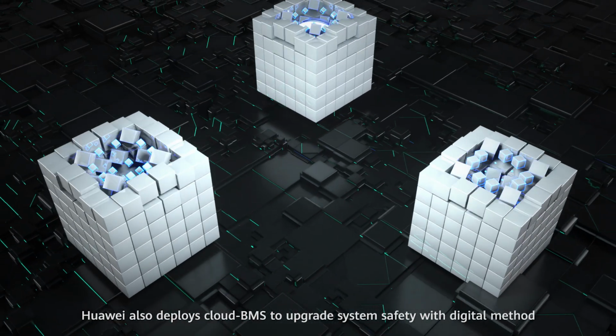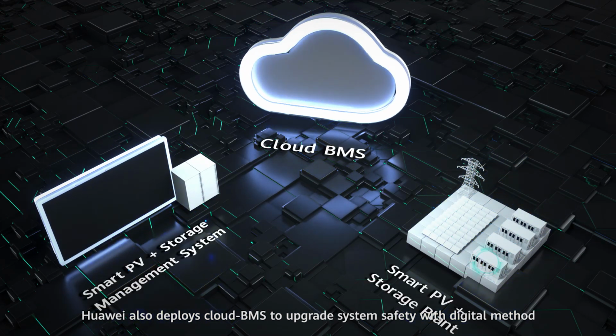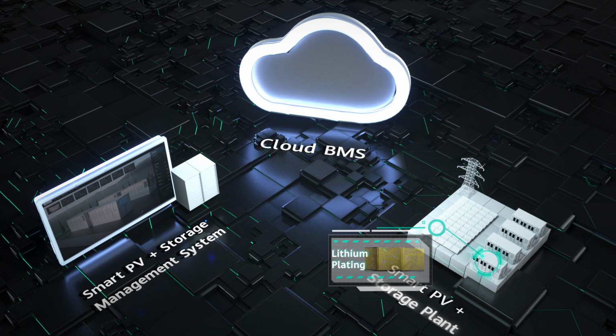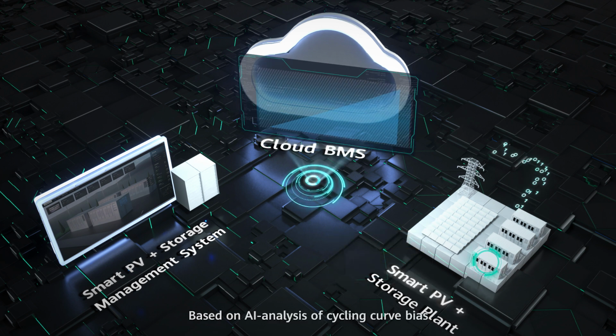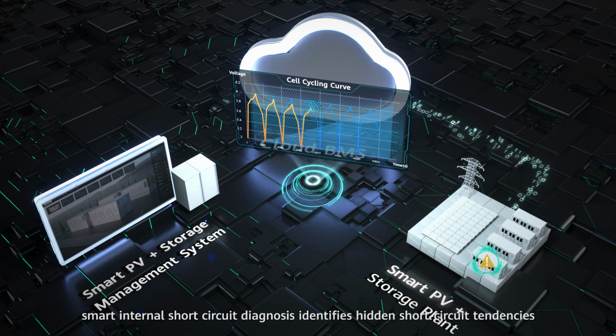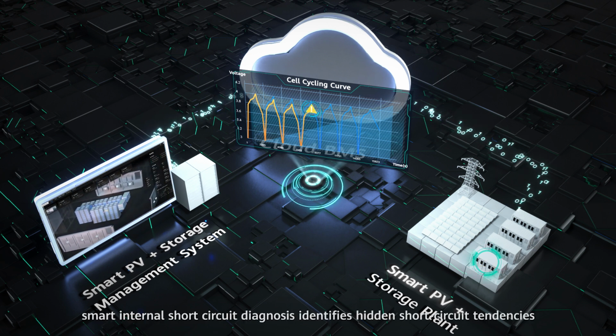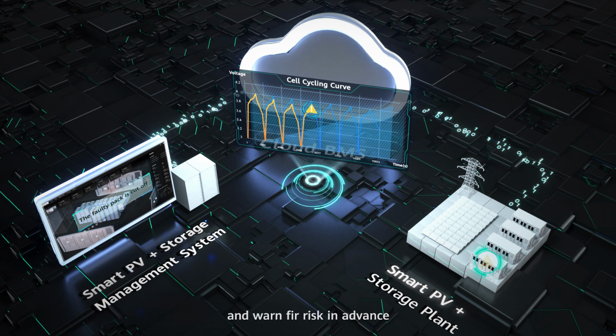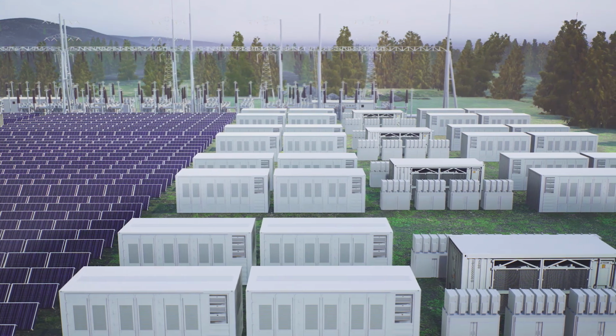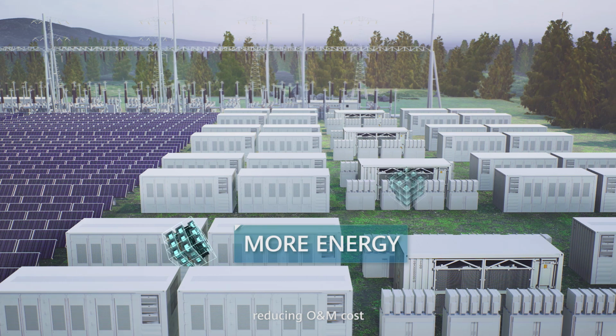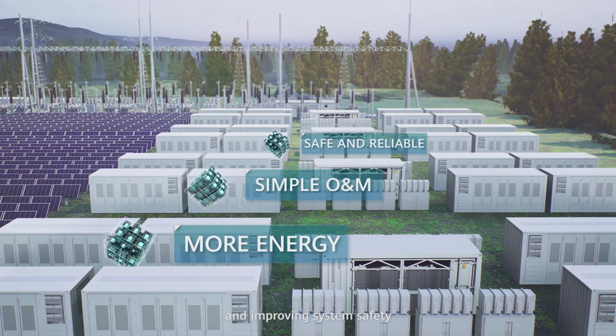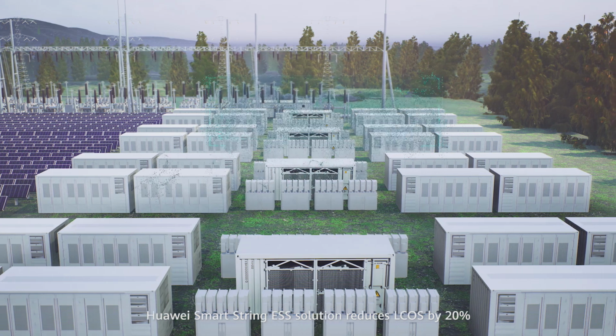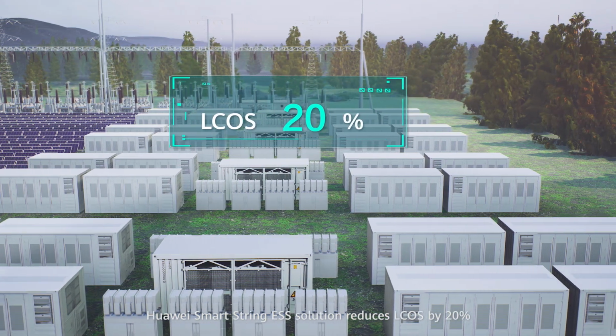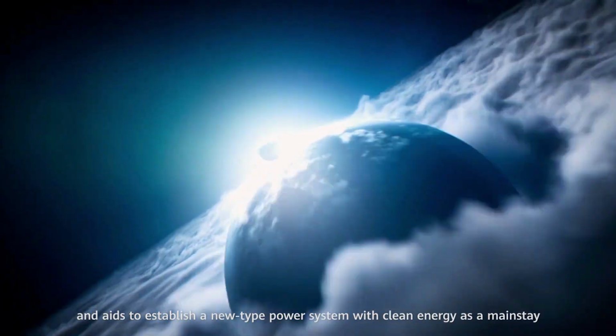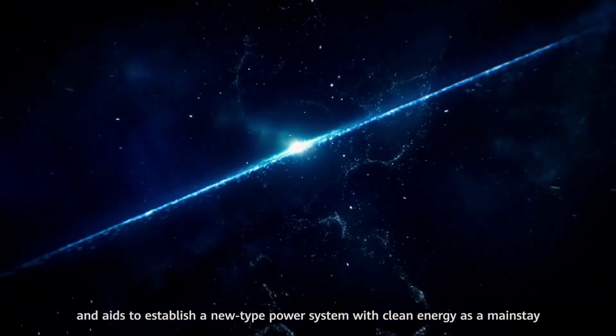Huawei also deploys cloud BMS to upgrade system safety with digital method. Based on AI analysis of cycling curve bias, Smart internal short circuit diagnosis identifies hidden short circuit tendencies and warns fire risk in advance. Via discharging more energy, reducing O&M cost, and improving system safety, Huawei's SmartString ESS solution reduces LCOS by 20% and aids to establish a new type power system with clean energy as a mainstay.